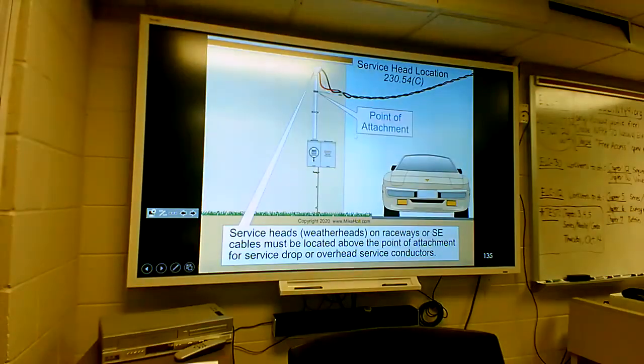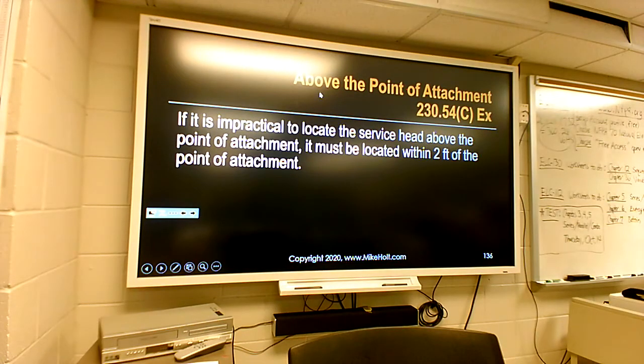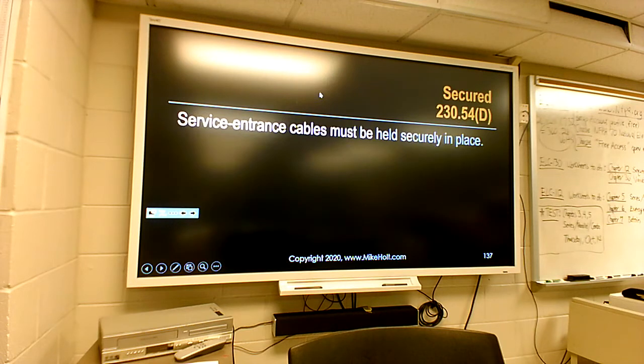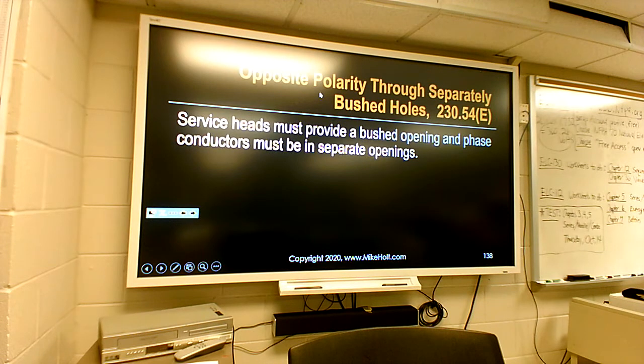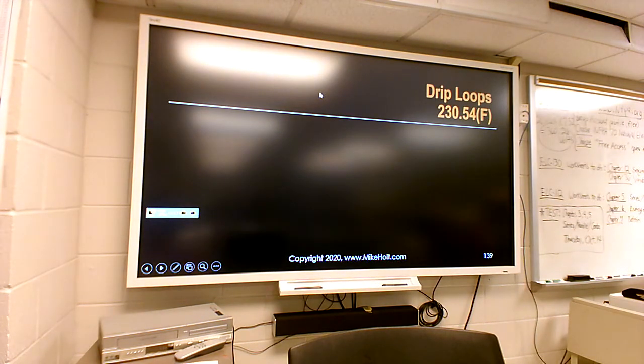Above the point of attachment, your weather heads must be located above the point of attachment for service drop or overhead conductors. Right. So obviously the service head has to be above this. It's got to be within 2 feet of the point of attachment. And your service head, your weather head, has to have separate openings for the conductors. And it has to include drip loops for rain to drip. So you'll notice there'll be a drip loop where your service entrance is. They do it that way so when the rain hits it can drip and not go in the weather head. It can't go in the weather head.